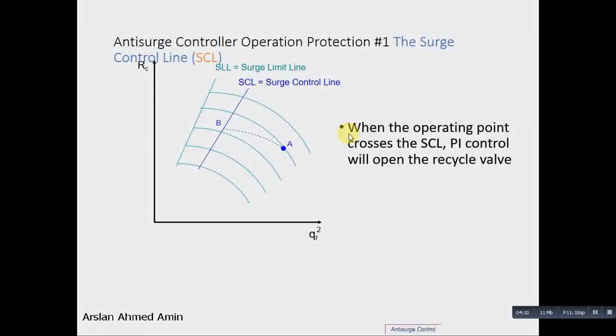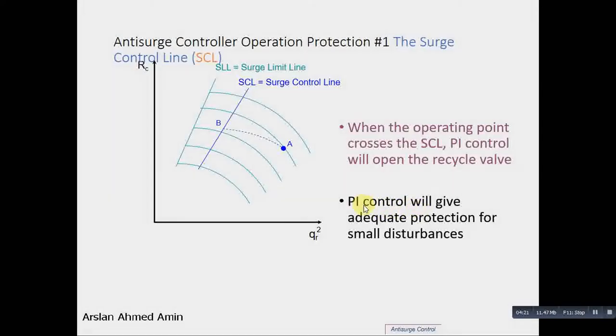So when the operating point crosses the SCL, surge control line, a PI control will open the recycle valve. A PI response, proportional and integral, will give adequate protection for small disturbances. PI control will provide stable control during slow disturbances near the surge location.